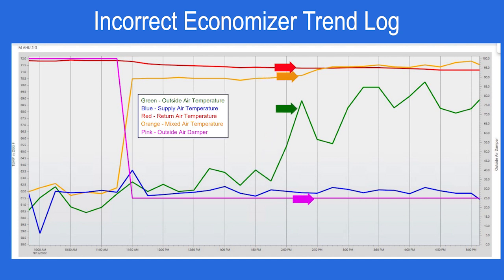You can see that the orange mixed air temperature line starts to track more with the return air temperature line. So we're really missing out here on a lot of opportunity to reap the benefits of that free cooling. In this case, the damper is modulating properly, so we probably don't have necessarily a stuck damper or linkage issue. It's probably more going to be a programming error. So that should be looked at and corrected to reprogram that to minimize the mechanical cooling.